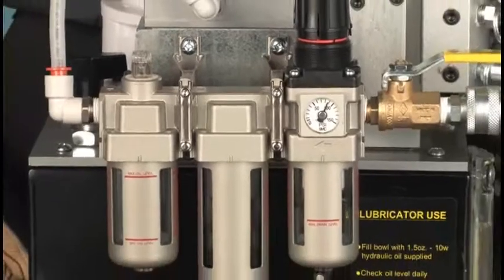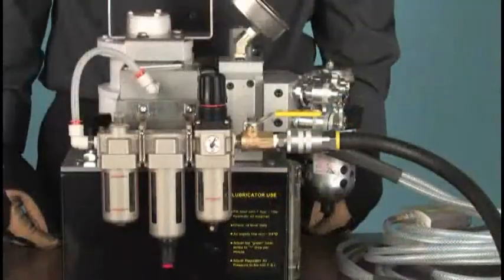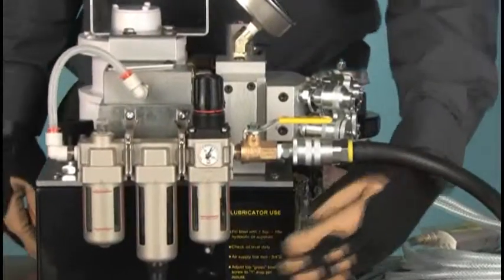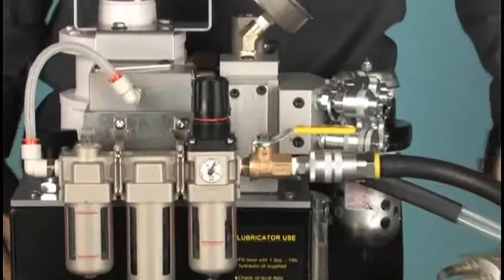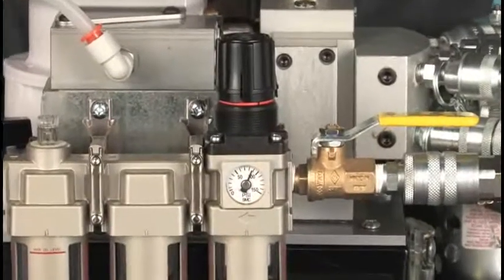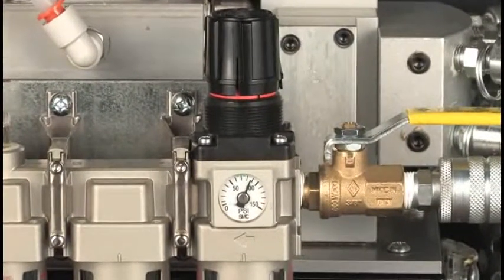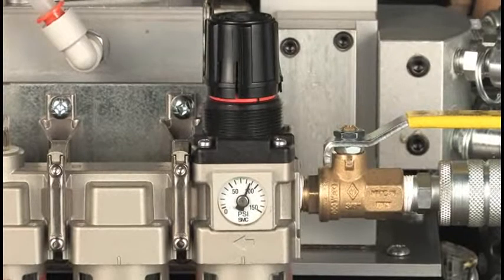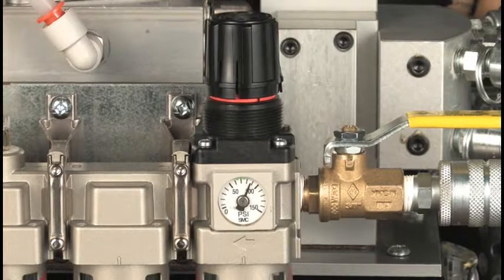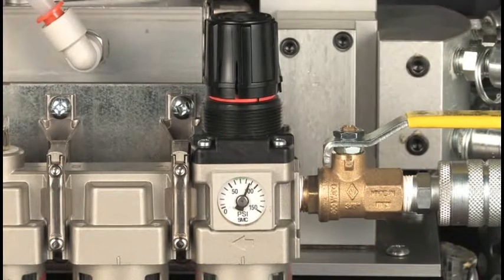The first unit after the main air valve is the pressure regulator. This is not to be confused with the regulator on the pump which controls hydraulic pressure. This one allows the operator to limit the incoming air pressure to a range from 80 to 120 PSI. About 100 PSI is usually ideal. Lift up and turn the knob on top in or out to adjust the pressure on its gauge.